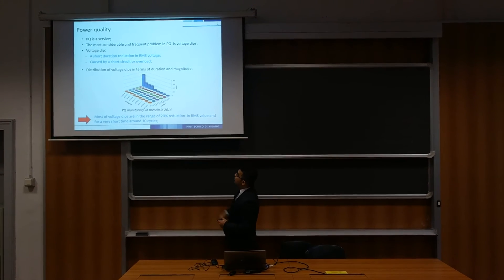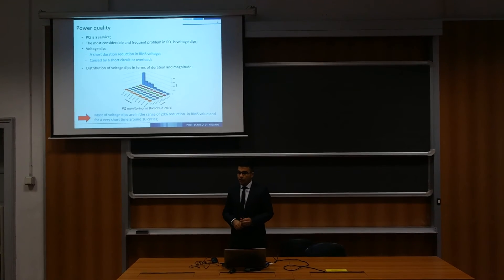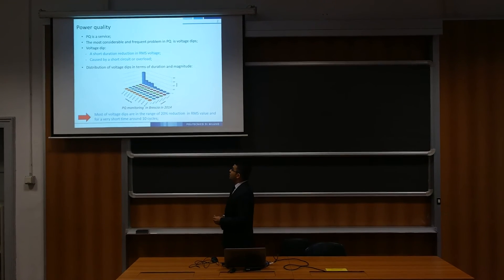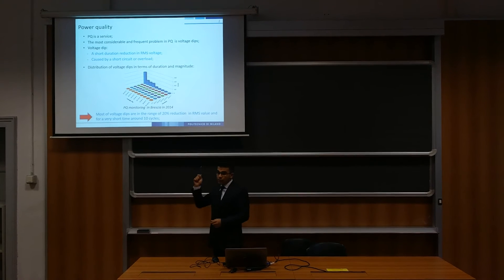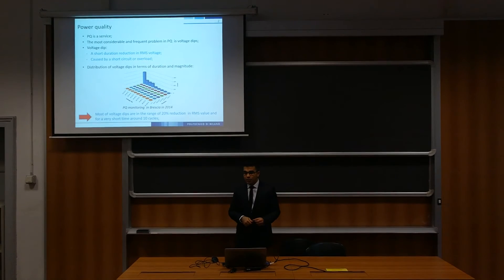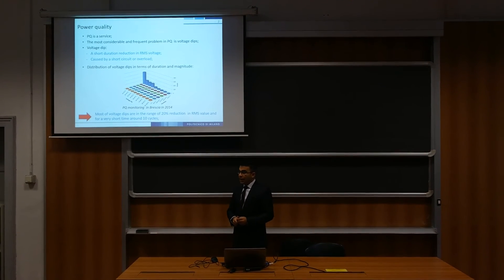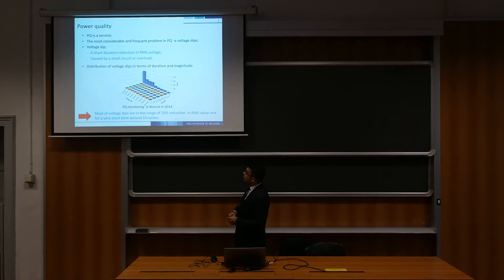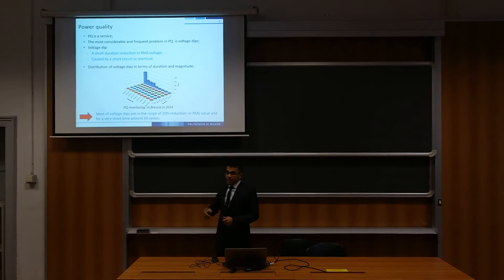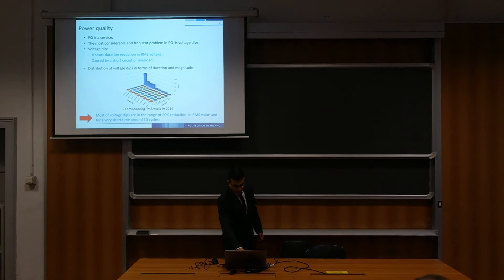In the graph, you can see the distribution of voltage dips in terms of duration and magnitude from a power quality survey in 2014 in Brescia. As you can see, most of the voltage dips are in the range of 20% reduction in magnitude and for a very short time, around 10 cycles. More or less the same trend is observed in other power quality surveys.